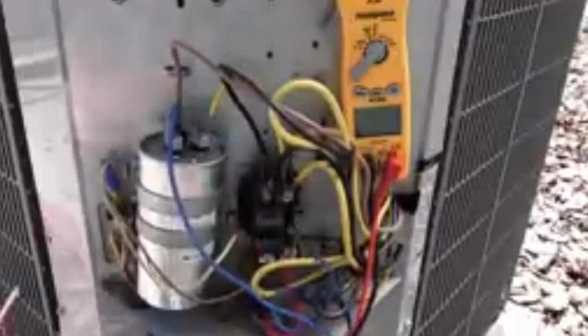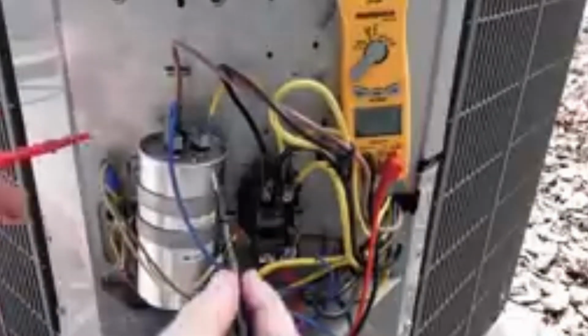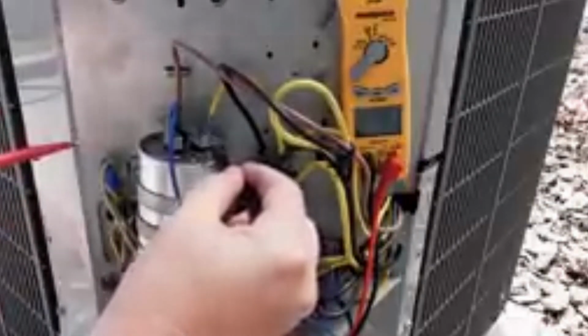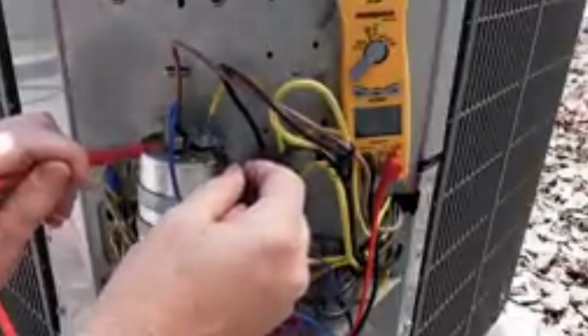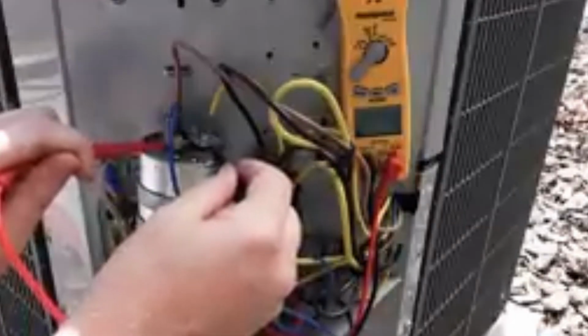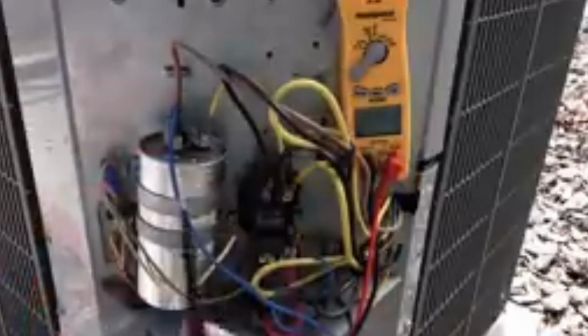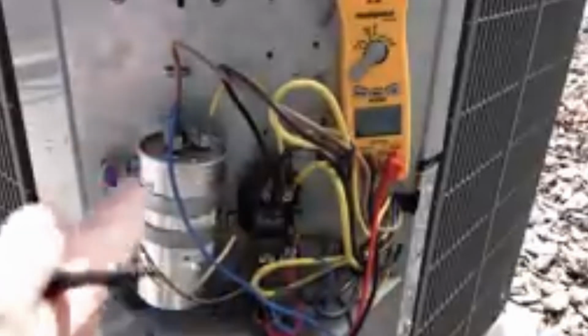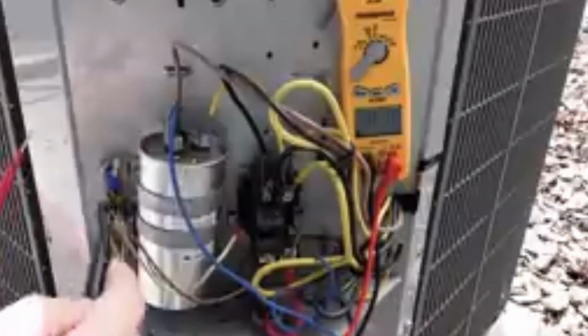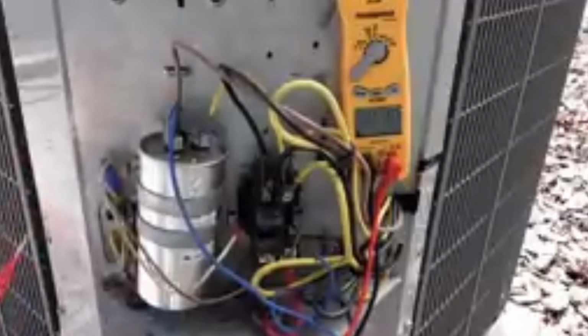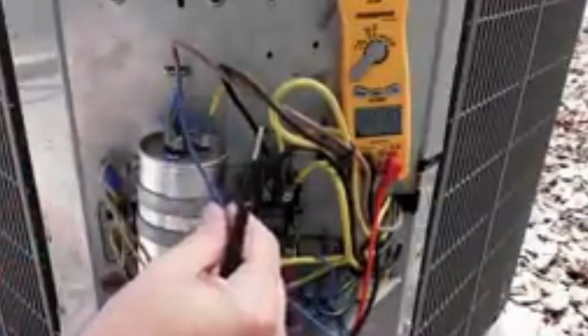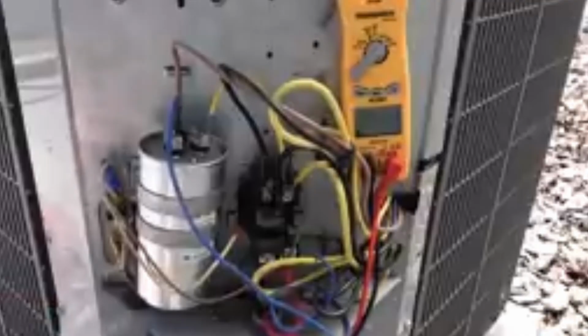You'll also show a slightly higher voltage when you measure in between common, or the C terminal on your capacitor, and your HERM terminal. You see we have 295 volts. That's the voltage incoming plus some back electromotive force being generated by the motor that we see on the capacitor. We can use that calculation as well as our current from our HERM terminal in order to calculate the capacitance on our capacitor while the system is running.